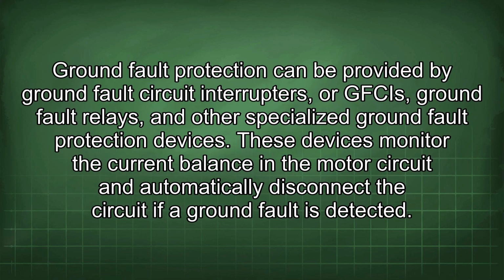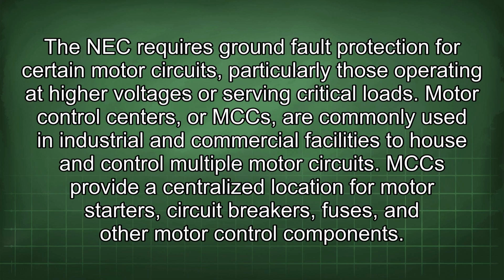Ground fault protection can be provided by ground fault circuit interrupters, or GFCIs, ground fault relays, and other specialized ground fault protection devices. These devices monitor the current balance in the motor circuit and automatically disconnect the circuit if a ground fault is detected. The NEC requires ground fault protection for certain motor circuits, particularly those operating at higher voltages or serving critical loads.